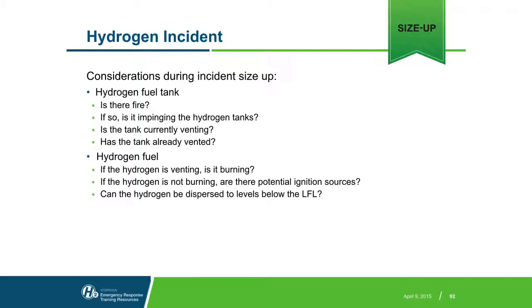So if the tanks are venting, is the hydrogen burning? Because these are high pressure vents, it's possible that you don't see flame until some distance from the actual point of the venting, because of the concentration and the velocity of the gas that's escaping. If it's on fire, let it burn itself out. Let the hydrogen vent and burn, because if you do extinguish the venting hydrogen that's ignited, you still have gas venting, and that could reignite and possibly be a worse situation. As it's burning, it's using itself up, and as soon as that hydrogen's gone, that flame extinguishes itself. In the meantime, you can be fighting the non-hydrogen fires conventionally.